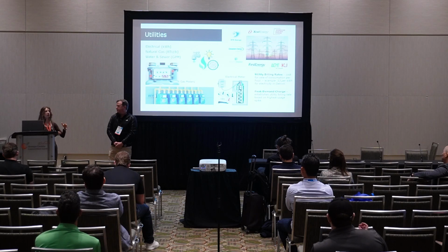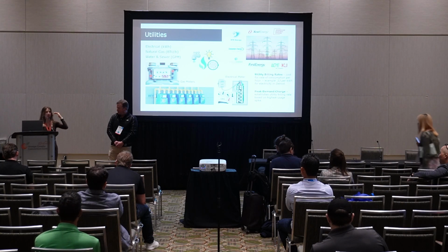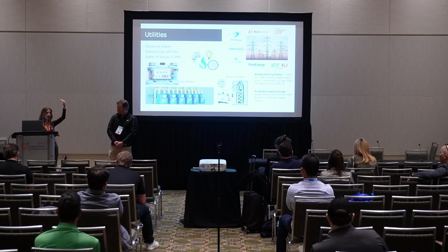So what was happening is the heat pump was running, and then at 8 o'clock the heat pump still hadn't heated up the building, so the boiler would come on. And 8 o'clock is when everyone's in the building turning on their computers, that's the peak. So this huge boiler load was being added to the existing peak, and demand charges were through the roof. The boiler comes on anyway because the heat pump can't cold start.